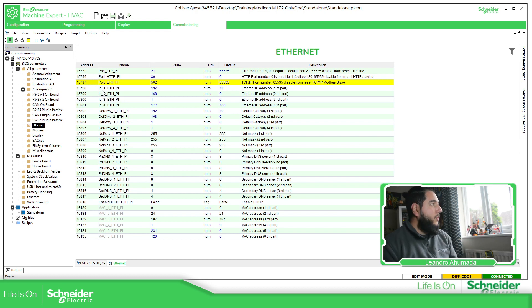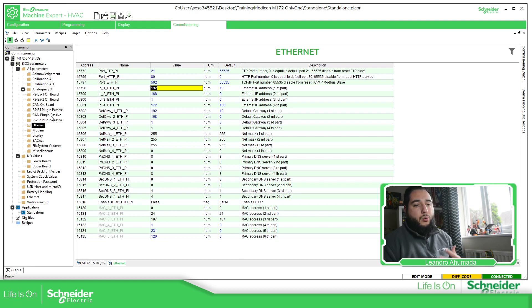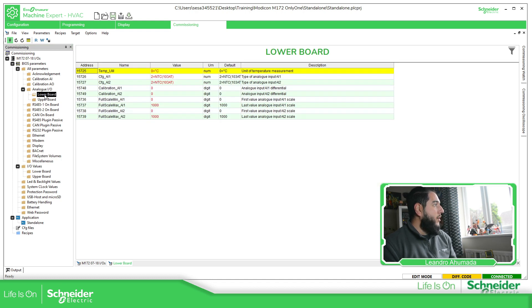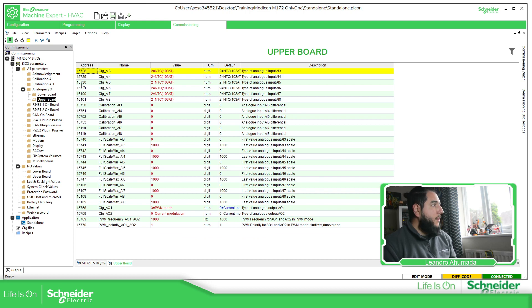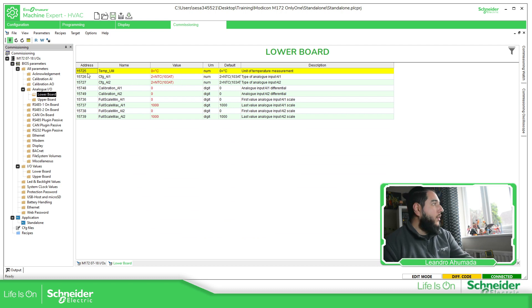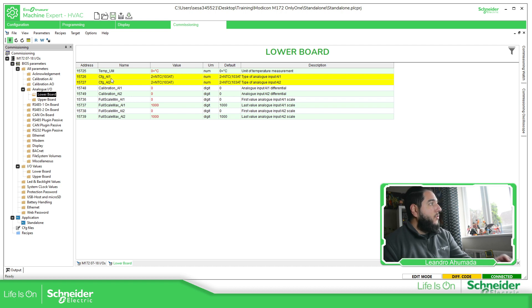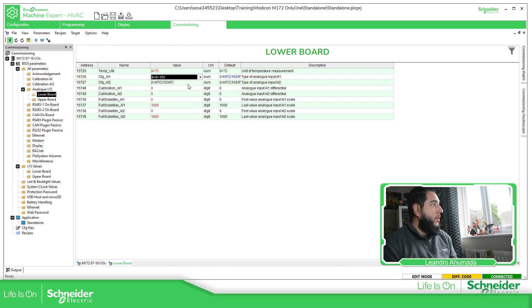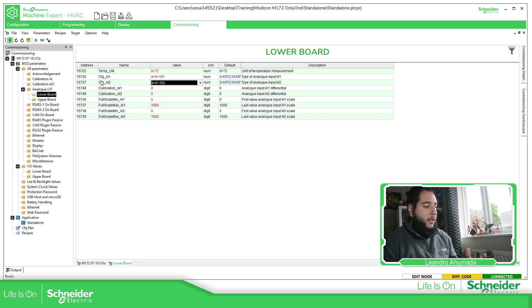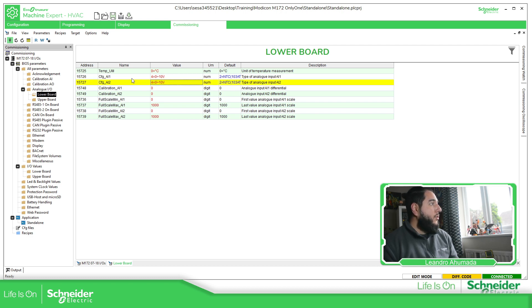If we want to make a modification, we just change the value and then write it. For example, to change the analog input configuration of the PLC, go to Analog IO, then Lower Board or Upper Board depending on your configuration, and make the changes you want. First let's read the current PLC configuration. For example, I can change an input to voltage mode. It's important to understand that this changes the impedance, so it's a good idea to disconnect any probe or sensor before making this change, then write the information to the controller.